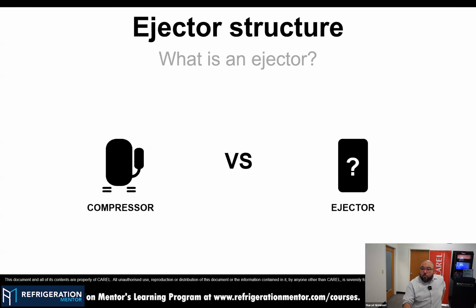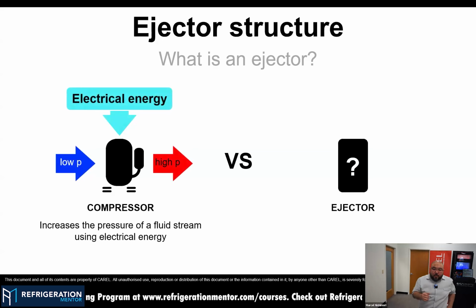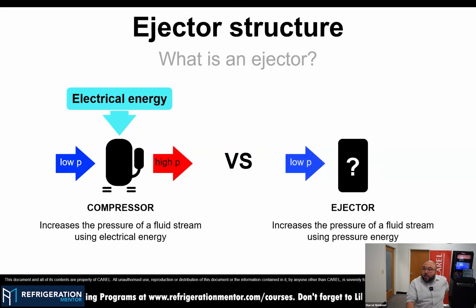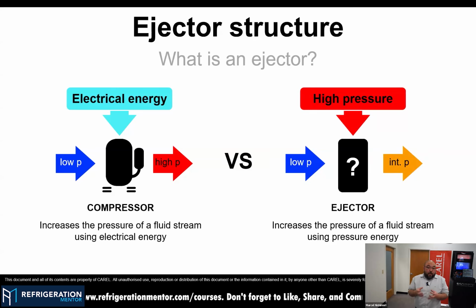So talking a little bit about the ejector, why is it an ejector and how should it work? So let's start from the beginning. Normally, when you have a compressor, you have the electrical power, so the energy coming electrically, making the compression from low pressure to high pressure side of the system, right? So you inject electrical power and then you make the compression. When we have an ejector, the difference here is that instead of having the electrical power as the main source of energy to make the compression, we can use the expansion of the refrigerant. So we are basically using the high pressure side of the transcritical system to make a compression from the low pressure side. I will explain this better in the next couple of slides. But the idea here is that we can basically compress refrigerant for free, without needing to add more electrical energy to that. So this is the main point.